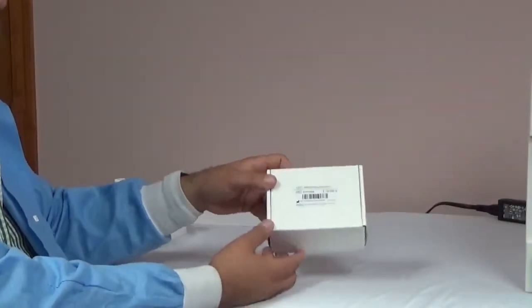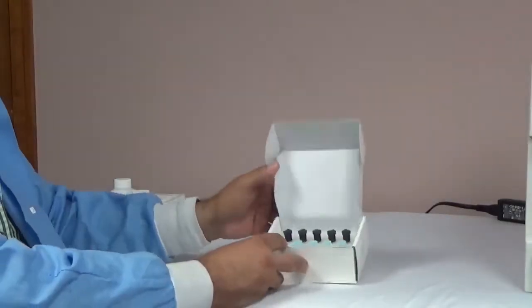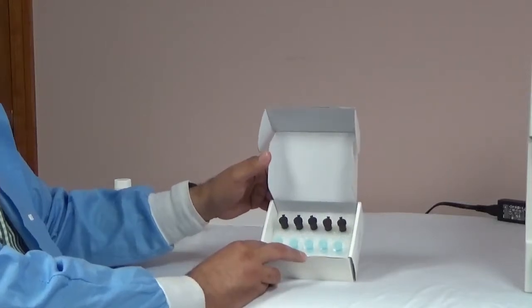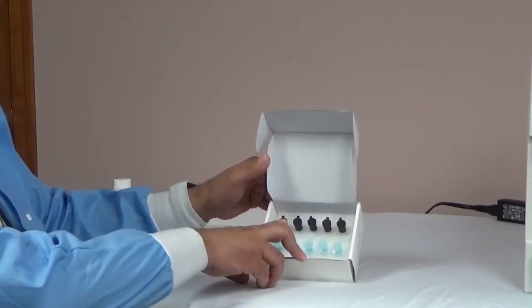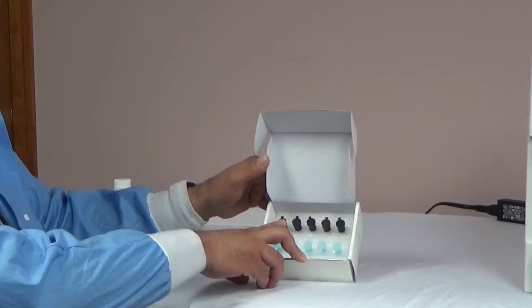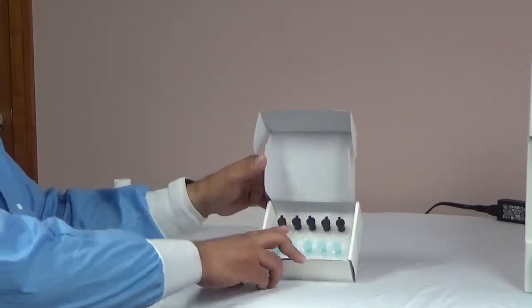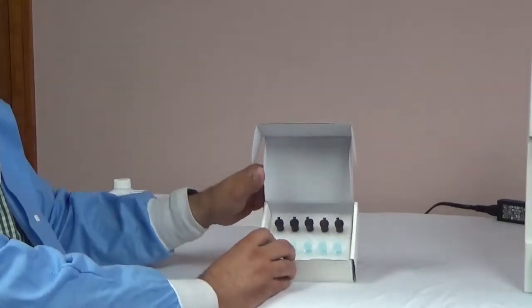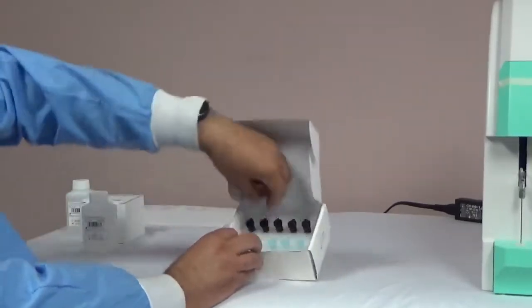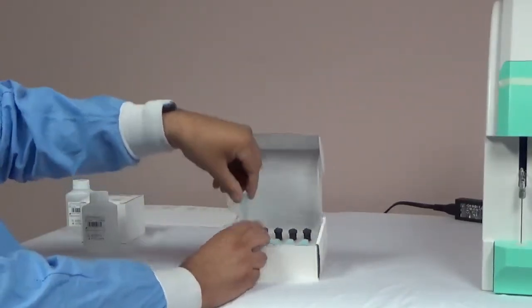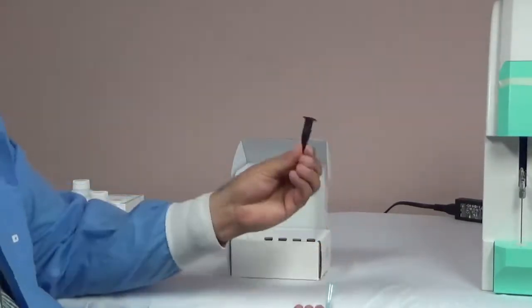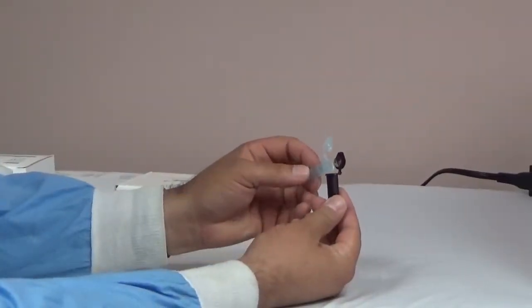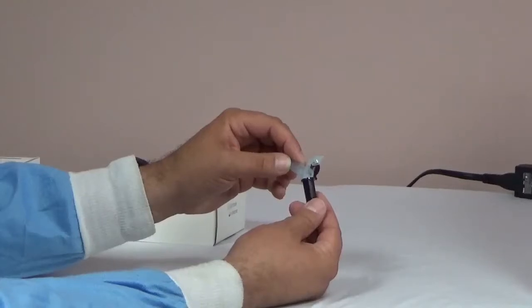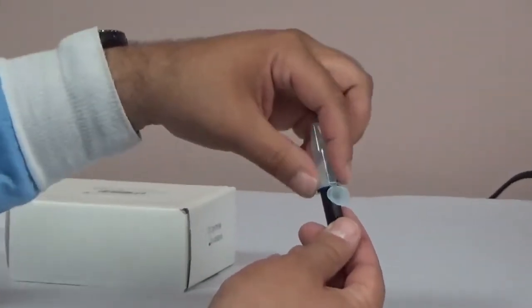Before running QC samples and patient samples, you will need to perform deproteinization. Deproteinizing is used to help keep the tubing of the analyzer clean and free of debris. Every analyzer will come with a deproteinizer kit. Inside the kit are 10 total vials. The dark vials contain an enzyme and the clear vials contain diluent. To prepare the solution, add the diluent to the enzyme, mix well until the powder is completely dissolved. Let stand for 5 minutes before use.